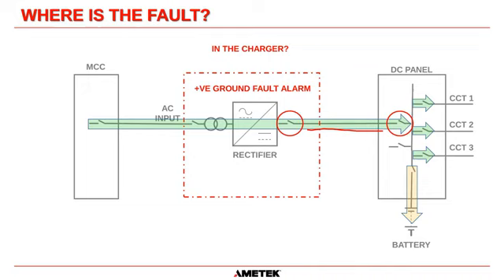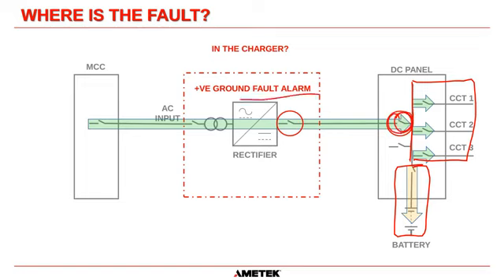So what we can do is we can close this output breaker back in again, and then we can open this breaker. And if the ground fault stays on, then now we know that the fault is in the cable between the charger and the DC panel. If the fault disappears, we now know that it can only be these load circuits here or this battery. So basically, if we open this breaker here and the ground fault clears on the charger, that means it has to be the load circuits or the battery that have the ground fault.